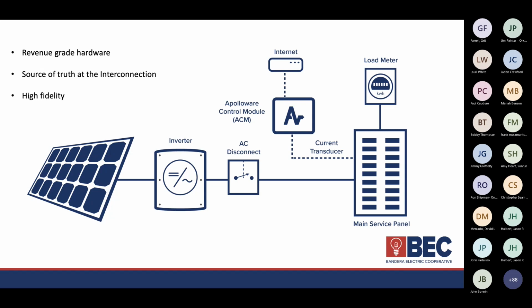If you look at every little rectangle on the main service panel, the big load usually has a dedicated circuit breaker for that - so like if it's a 50 amp, my HVAC's 100 amp, 50 amp pool pump, whatever. Once we identify what that circuit is, we can put it into the system. That's how we do the pool pumps, the HVACs. We identify that because we not only use this for DER monitoring, but we use it as energy feedback as part of our energy efficiency program.